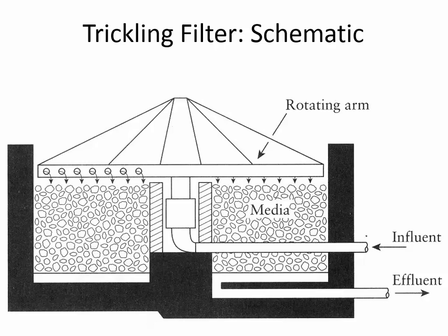So would you add dissolved oxygen to that water itself? No. What we'd have is at the bottom of the rocks, a stand that the rocks are supported on, like a rack, maybe a table with holes in it, and the air can naturally diffuse upwards. So this isn't fully saturated with water. It's mostly air inside of here, and so air is breathing in from below and from the top, and the water is just passing through and coating the rocks, getting them wet, but the voids between rocks is mostly air.